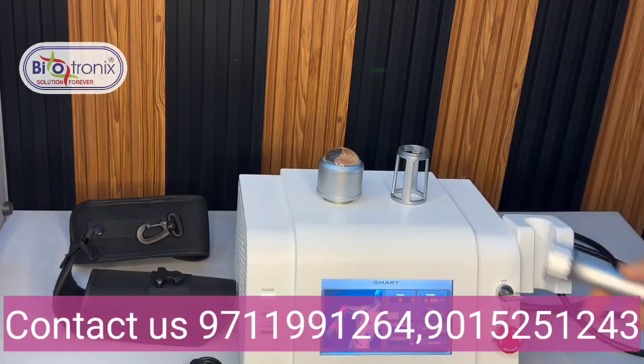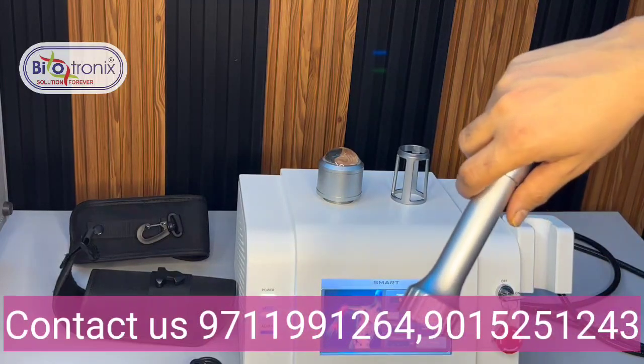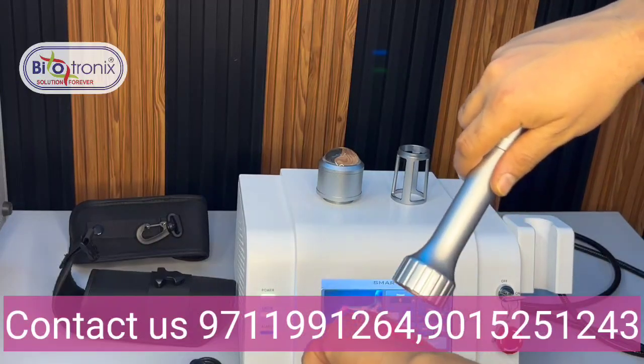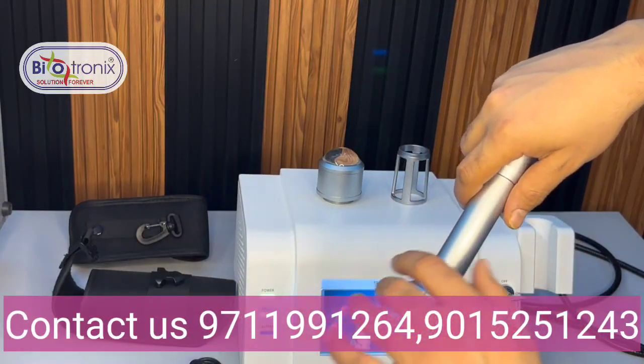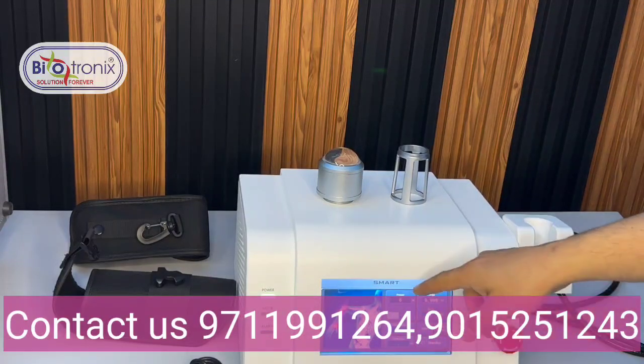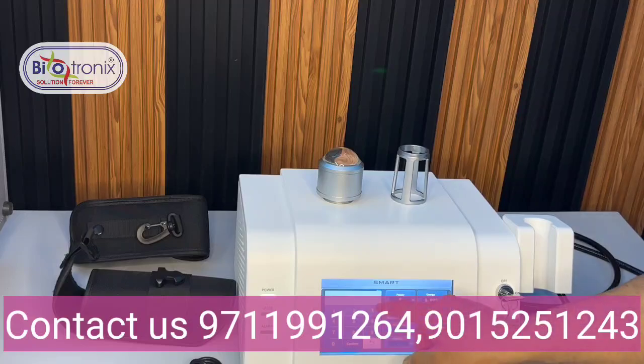I have put on the protection glasses. Now you can see I press the standby. Now you can see laser is ready, and you can see the probe is now activated and it's showing laser, but it's not giving me the output. It's just showing me the laser. Before starting, I will show you all the parameters. Like I'm selecting the 10 watt, the maximum power, and you can see this is the time section. Like I selected 15 minutes, confirm, and this is the continuous mode. This is the pulse mode. In the continuous mode, pulse width has nothing to do with it. In the pulse mode, I can select and put some value which I need.